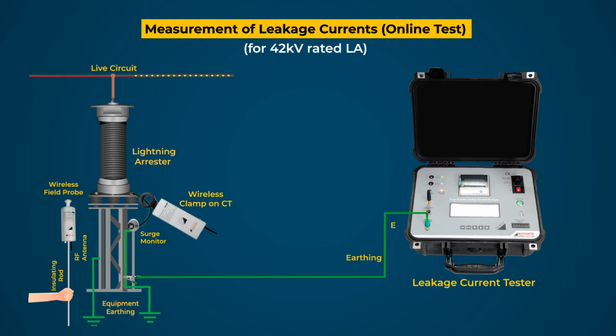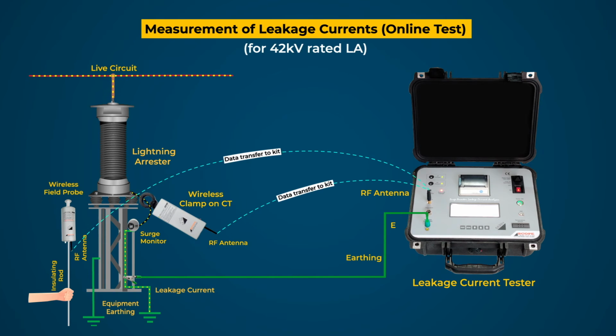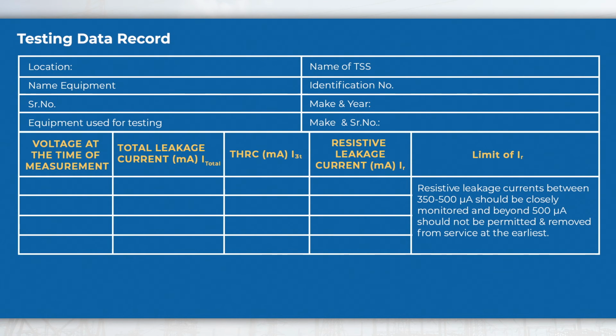Then start the test, and the leakage current and their components and the harmonics in supply are measured by clamp on CT and field probe. This collected data is transferred to the test kit. After getting the data, the kit shows the total leakage current and the resistive component of leakage current and the most important third harmonic component of resistive leakage current. The value of leakage current shall be recorded, and in case of abrupt variation or very high leakage current, the concerned lightning arrestor should be taken out from the service for detailed investigation. Testing data may be recorded in this format for further investigation and future reference.